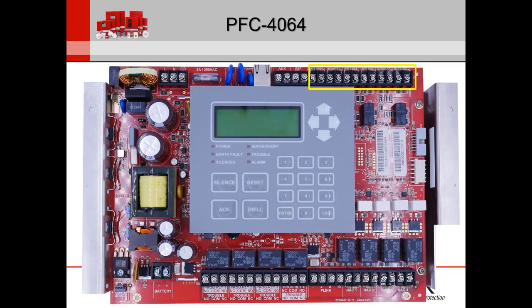The IDC circuits are listed to work with two-wire smoke detectors. Most people ask what two-wire smoke detectors are listed — the System Sensor 2WB does work with this, since that's like the number one conventional smoke detector used nationwide. Then you have your notification circuits. There's also a reference EOL terminal that confuses people — they think it's for the input circuits, but it's actually for the notification circuits. By default, we use a 5.1K end-of-line resistor; however, with the reference EOL you can change this between 2K to 27K.